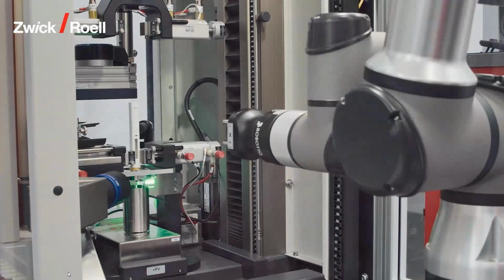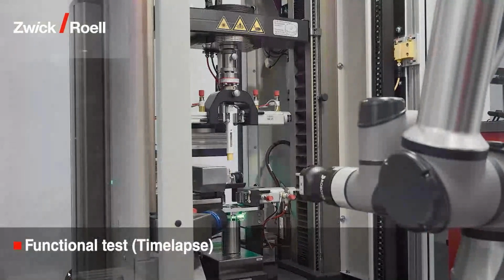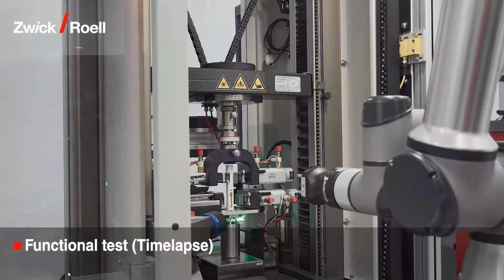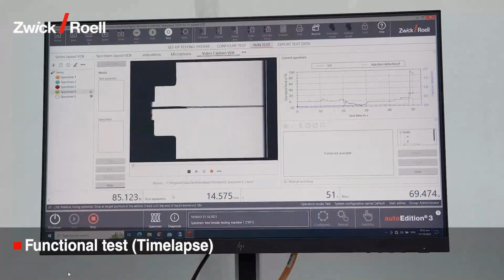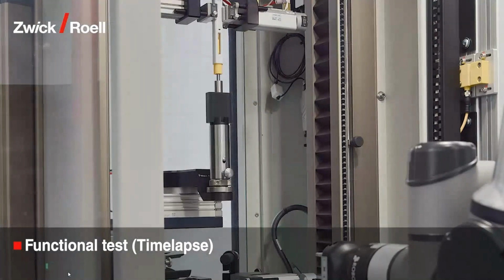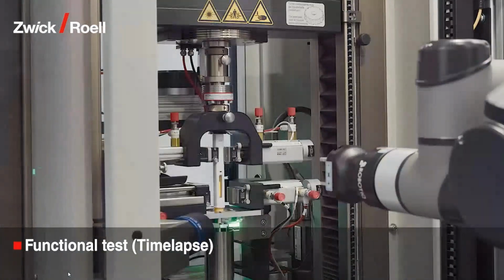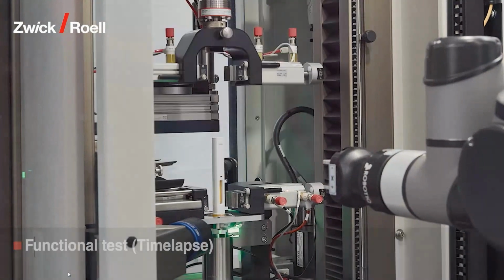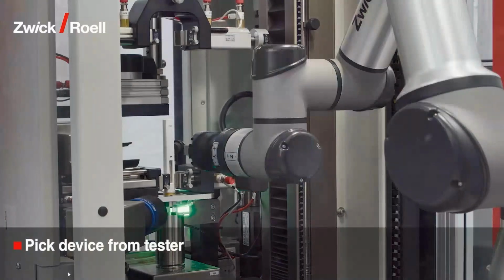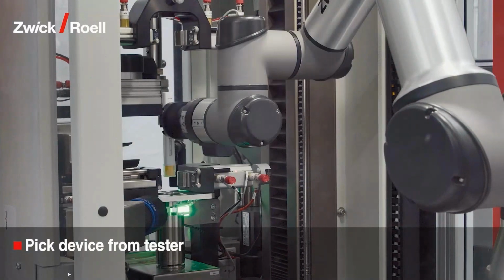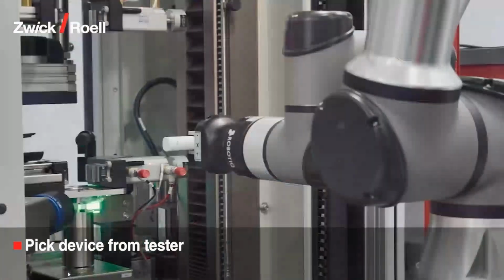Then now it's fast motion, as the focus of this movie is on the automation. So it's the functional test on this auto-injector. In this case, it's the YpsoMate pen. You may have recognized it. So we are checking the needle shield, and then we are picking the device from the tester, placing it back in the magazine.